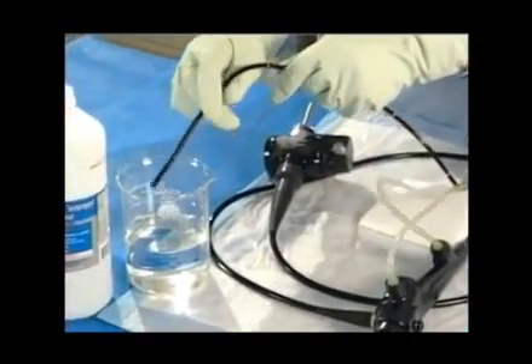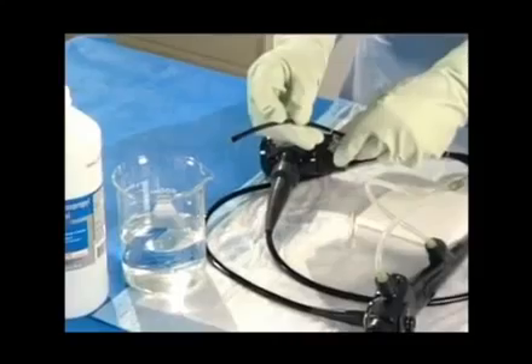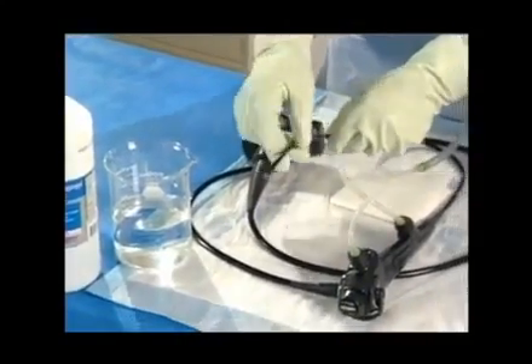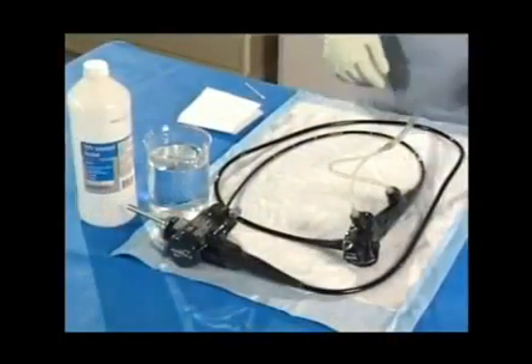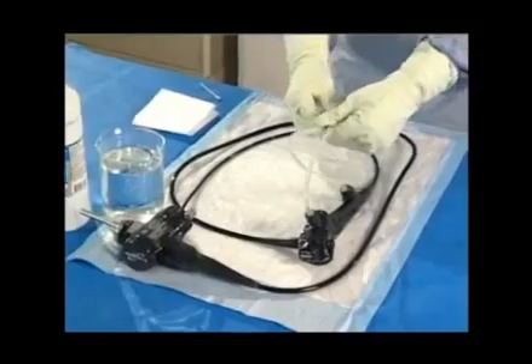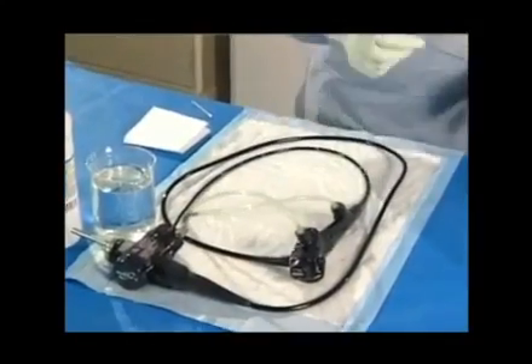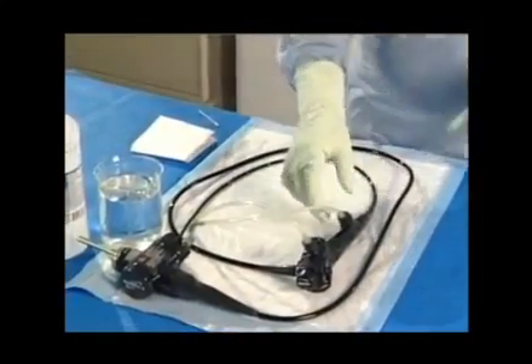Remove the distal tip from the alcohol and aspirate air for 20 seconds. Now that the channels have been flushed, disconnect the suction tube and the suction cleaning adapter.